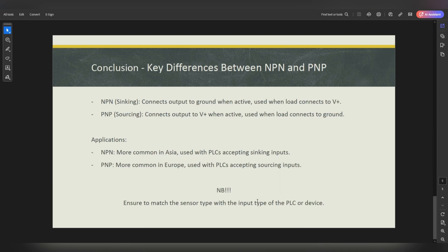Just to conclude the presentation before showing you the wiring in ePlan: with NPN sensors, the sinking sensors, they connect the output to the ground when active and are used when the load is connected to the positive — it's always connected to the positive. With the PNP sensor, it connects the output to the positive when active — the load is always connected to the ground, just patiently waiting for 24 volts.